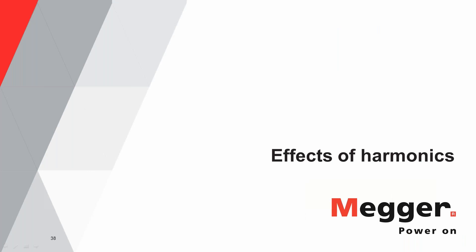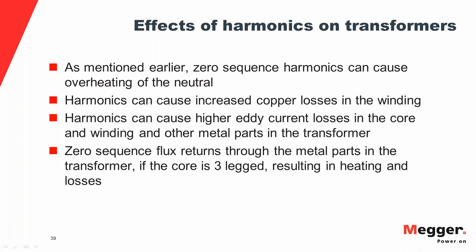What effects do harmonics have on the system? We already discussed how zero-sequence harmonics can cause overheating of the neutral. Harmonics also cause increased copper loss or I²R losses — since harmonics are current, they add to the heating effect when current flows through a conductor. Harmonics can also cause eddy current losses: when current flows in the vicinity of a metal part, the current's field induces local EMFs that set up circulating currents — eddy currents — within the metal part, and those eddy currents cause losses.